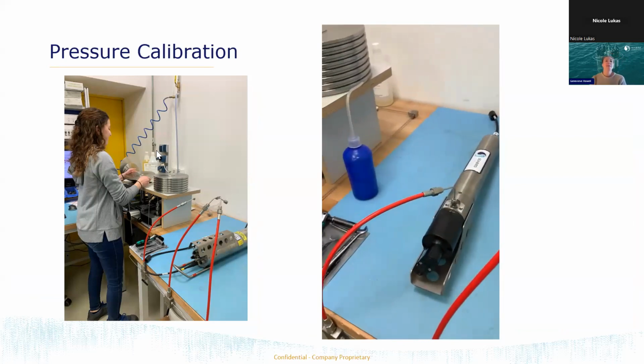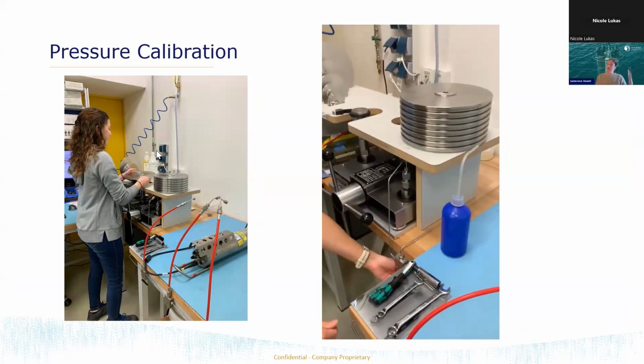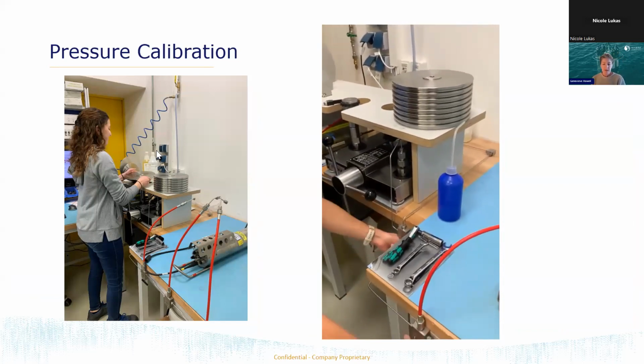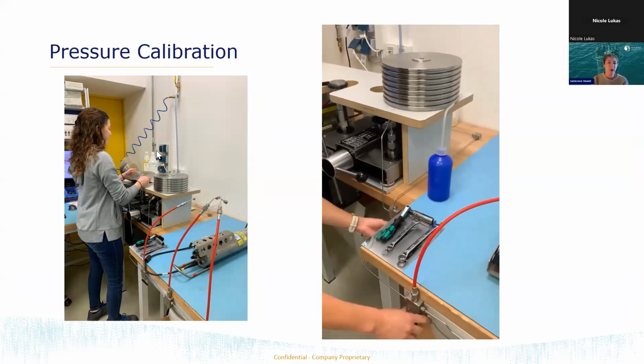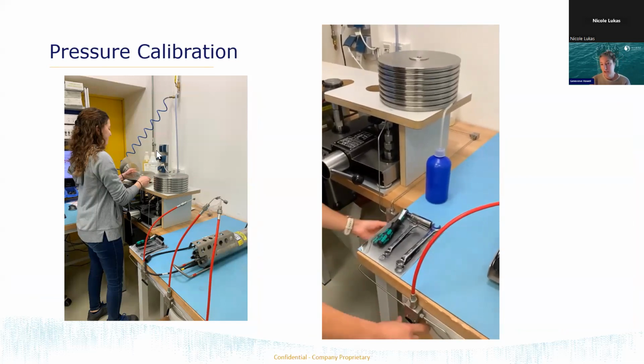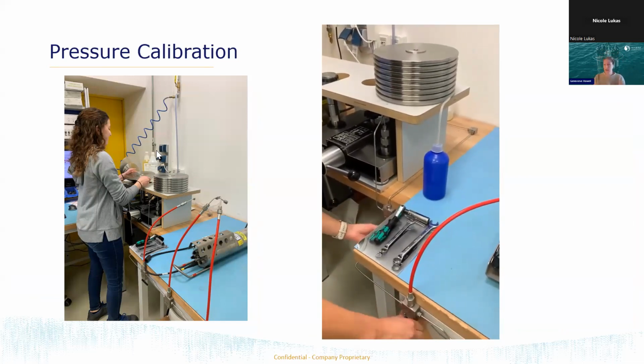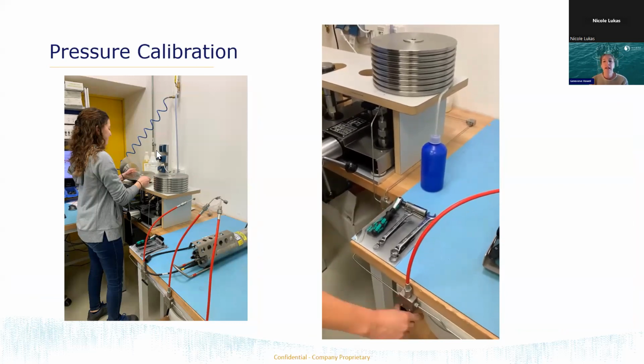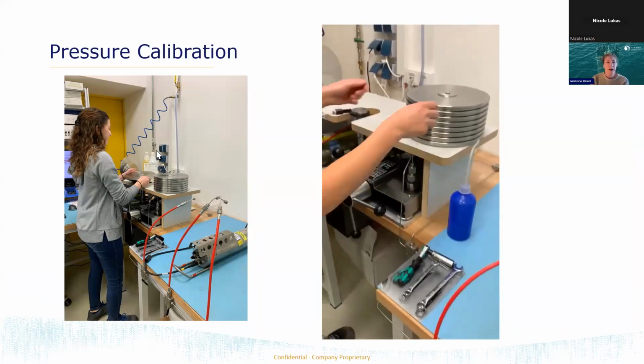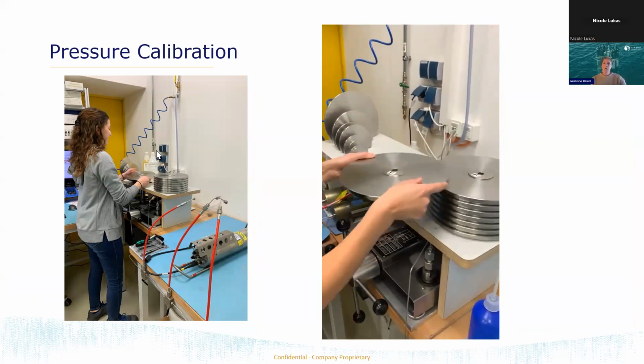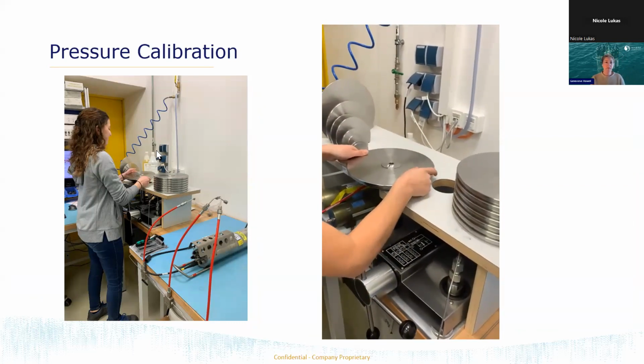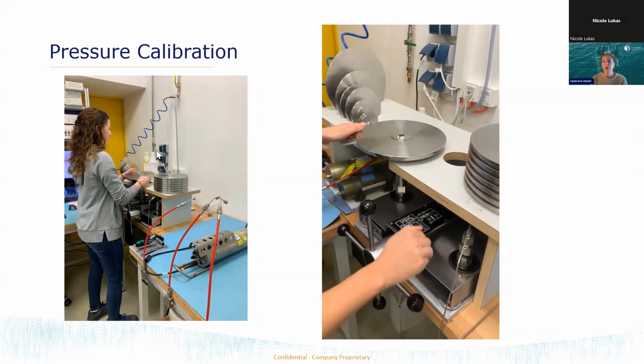There we go. So pressure calibration. If your instrument has pressure, then we perform this work, which is actually a characterization. So we don't do a true pressure calibration. We use a digiquartz reference. So that digiquartz sensor is what we're relying on to tell us the true pressure that we're creating.